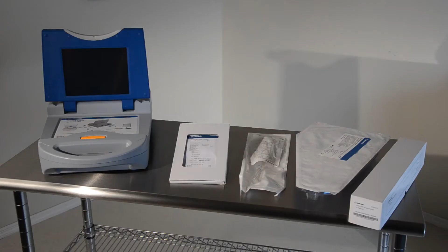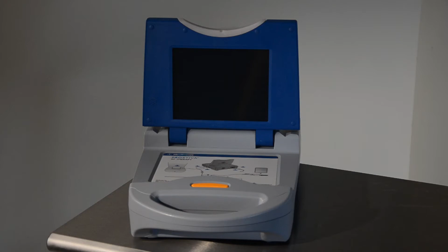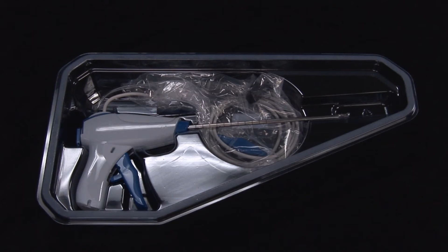Primary components of the Prostiva RF therapy system include the radio frequency generator, the grounding pad, the telescope, and the disposable handpiece kit, which contains the handpiece, tubing system, and return electrode. The generator is a portable, line-powered, dual-channel generator capable of producing up to 50 watts per channel. The generator produces RF energy at 473 kilohertz. The handpiece, including the RF cable, is packaged as a complete sterile assembly, which includes 2 insulating needles. The disposable handpiece kit is a sterile, single-use medical device. After it is used, it should be disposed of according to local environmental requirements.